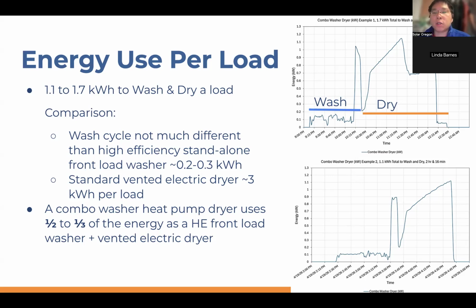Another thing that's interesting to note on these graphs is the peaks. These peaks are really quite low. A typical electric dryer has a peak of about 3 kilowatts. These are just above 1 kilowatt, and the reason they need to manage that peak is because these are on 120 volt circuits, and on a 120 volt circuit you can only draw so many amps, and you have half the voltage. The nice thing is that even with half the voltage and not as many amps, it's okay, because heat pump vapor compression cycle systems are very efficient, and so they don't need that much electricity in order to produce the heat necessary to dry the clothes.